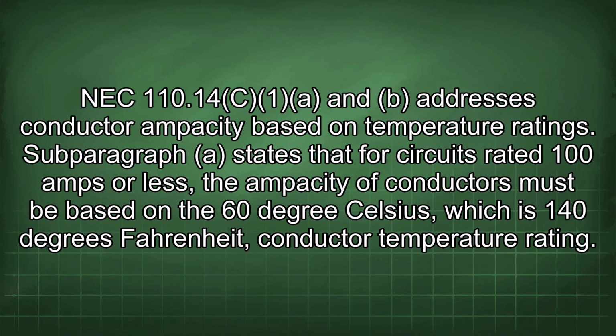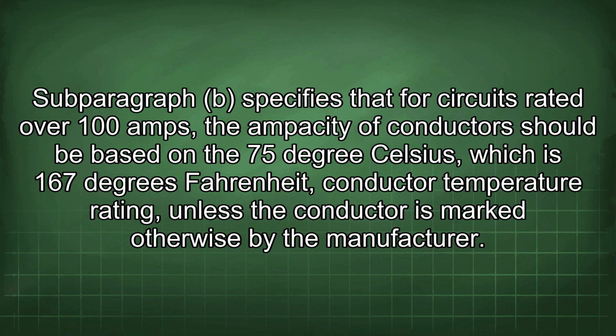NEC 110.14(C) addresses conductor ampacity based on temperature ratings. Subparagraph A states that for circuits rated 100 amps or less, the ampacity of conductors must be based on the 60 degrees Celsius, which is 140 degrees Fahrenheit, conductor temperature rating. Subparagraph B specifies that for circuits rated over 100 amps, the ampacity of conductors should be based on the 75 degrees Celsius, which is 167 degrees Fahrenheit, conductor temperature rating, unless the conductor is marked otherwise by the manufacturer.